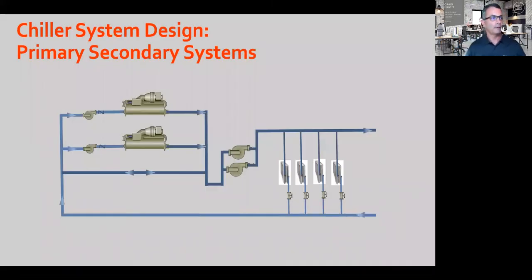So let's touch on primary secondary systems. Since the 1970s, variable flow requirements were satisfied using primary secondary systems. There's a primary pump for each chiller and secondary pumps that pump chilled water out to the building load. So it pumps in 2 loops. It also has a bypass line you see here just below the chillers.